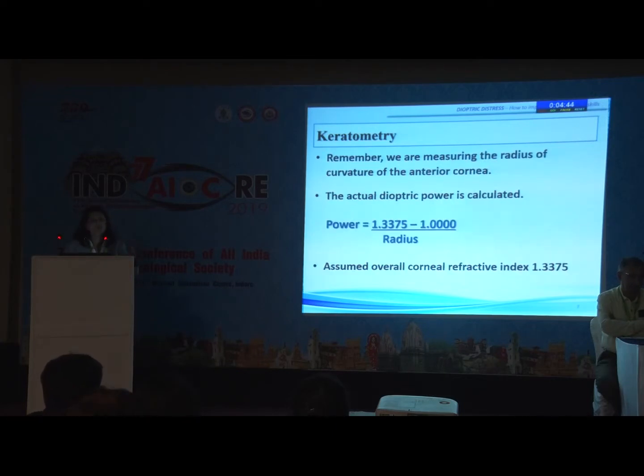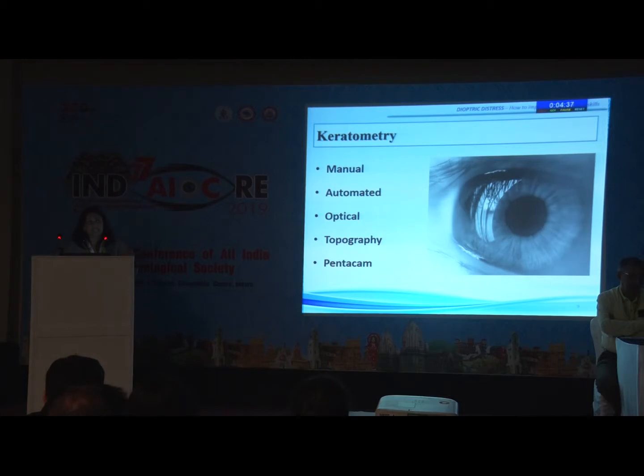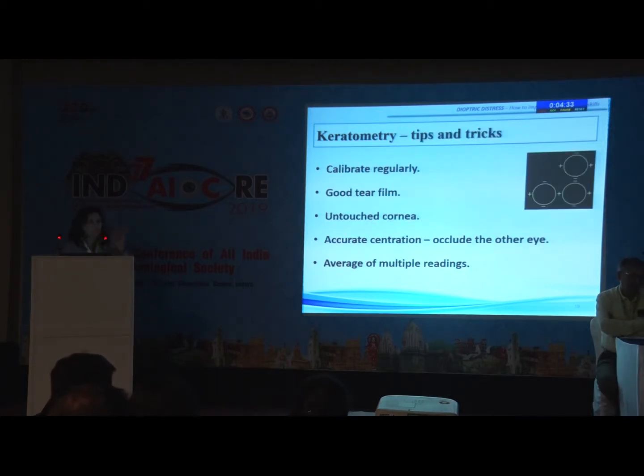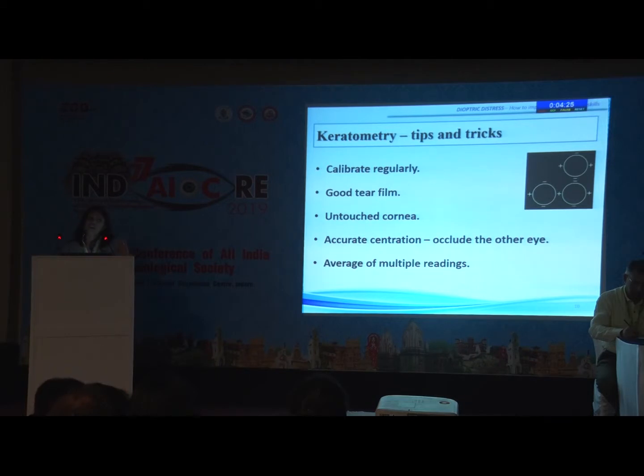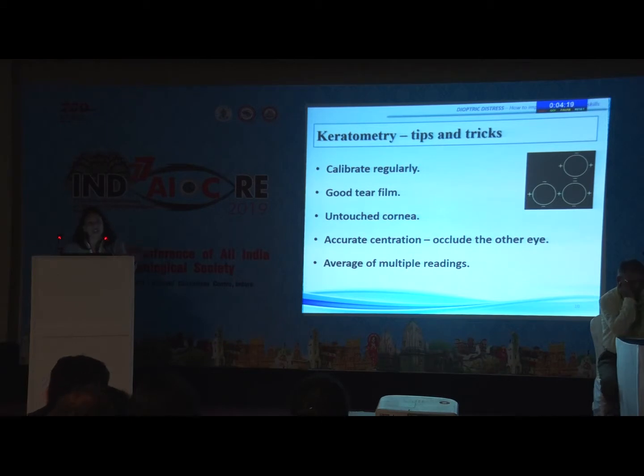Keratometry is based on using the refractive index of the cornea, 1.3375, and using this formula. The actual diopter power is calculated based on that. There are various modalities to measure this. Always remember to calibrate your instrument regularly. Always have a good tear film and untouched cornea. You should not have done any applanation, any gonioscopy, or any contact ultrasonic measurements — no contact procedure should have been done on the cornea before you take your keratometric measurements.